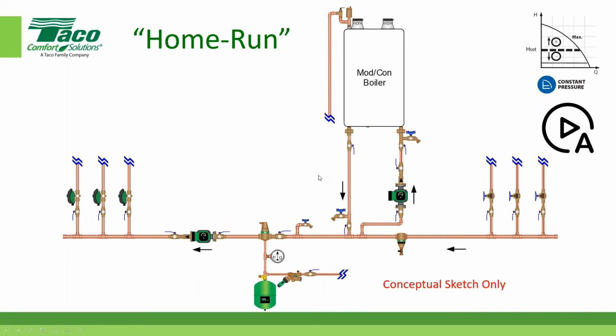Now let's look at probably the primary application for constant pressure. I'll call this home run. Actually, it's not what I call it, it's what Siegenthaler calls it. Our industry calls it that. What I mean by that is we have a boiler, we have some near boiler piping, and it's all in the same room with a header that's sized appropriately. And I've got 3 supplies and 3 corresponding returns coming back to the boiler room area. So all this piping here is generally short. Again, that's what we'll call a home run application.